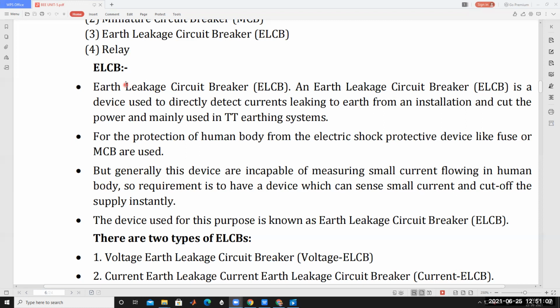That is why ELCBs are used for the protection of the human body from electric shock. For protection of the human body from electric shock, protective devices like fuses or MCBs are generally used. But generally, these devices are incapable of measuring the small current flowing in the human body. So the requirement is to have a device which can sense the small current and cut off the supply instantly.